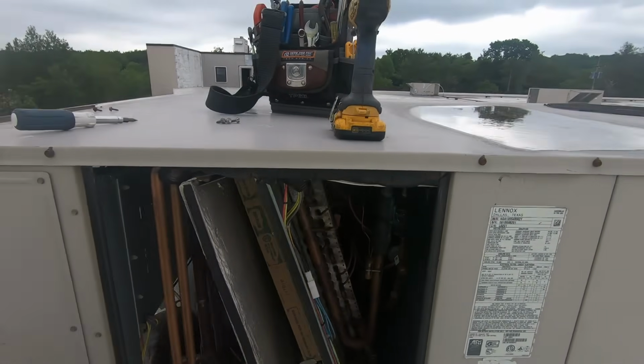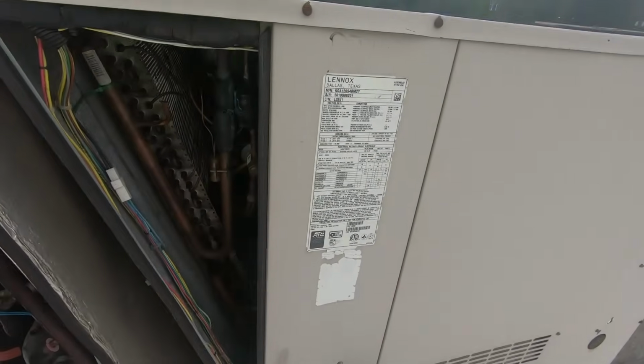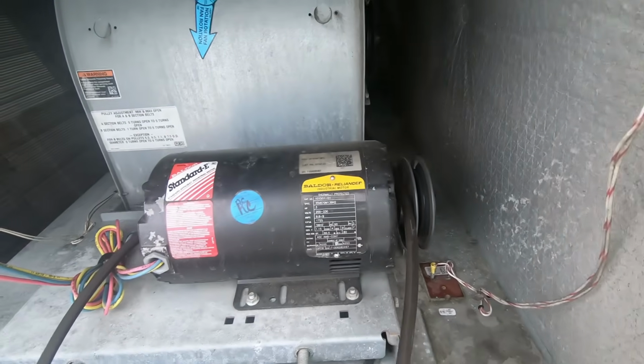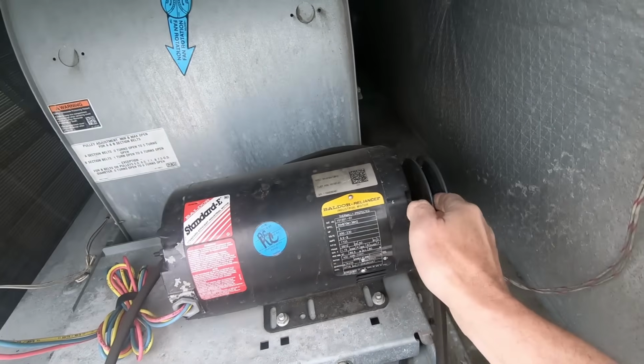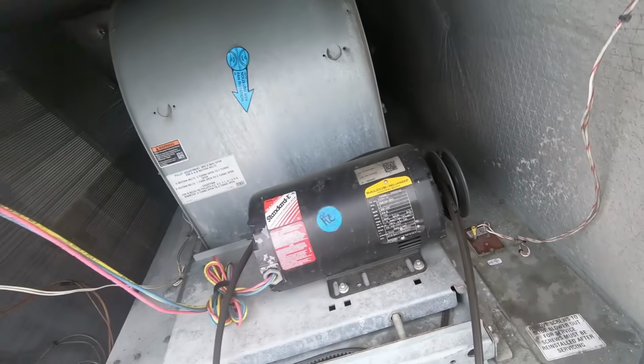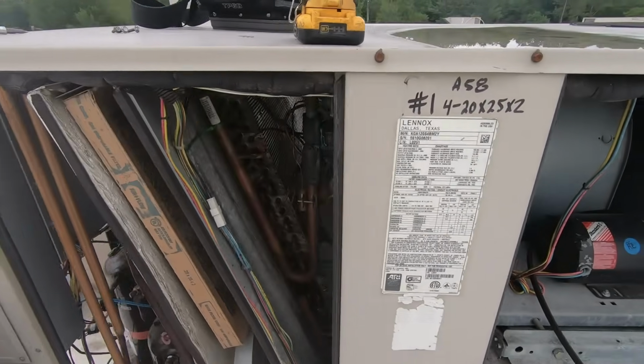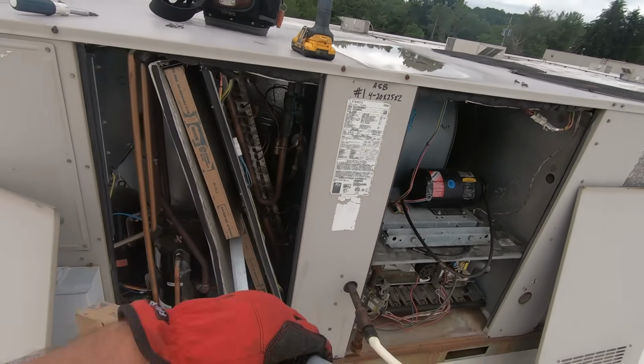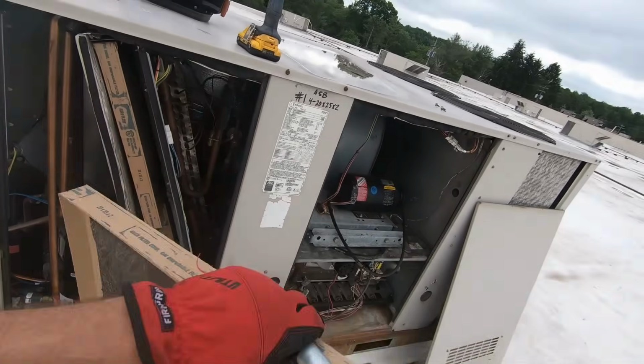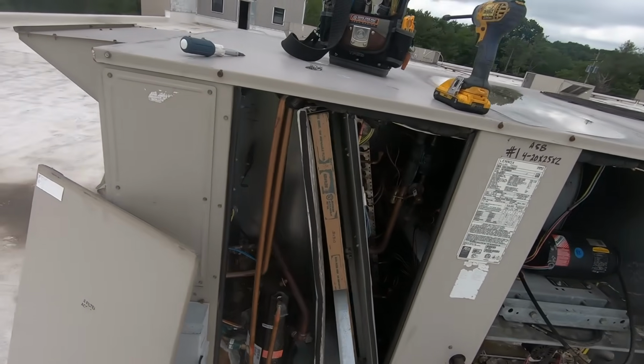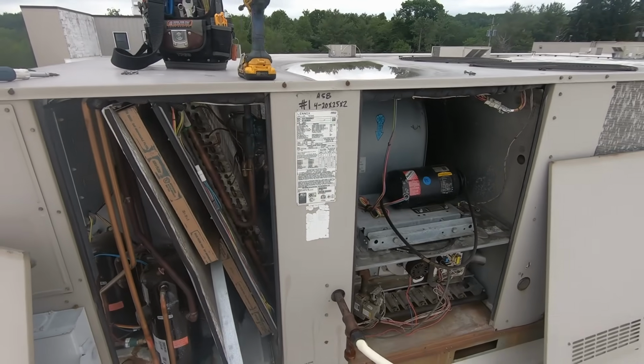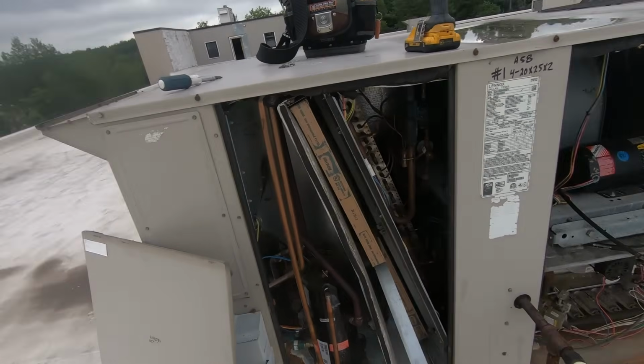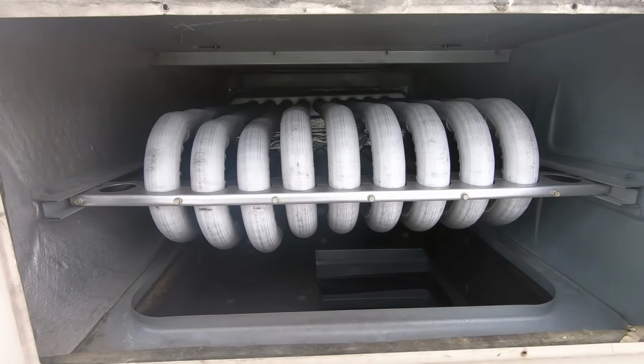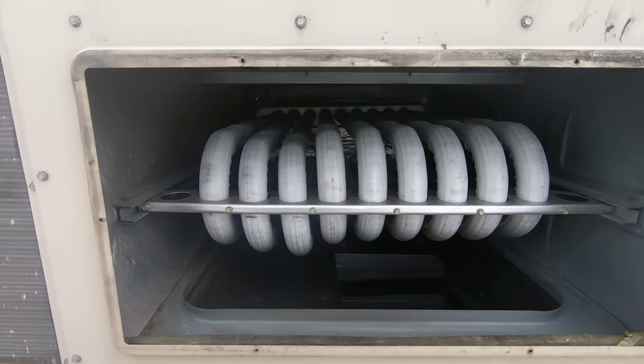Shut it off. Belt's gonna be freaking beat for sure. The belt's worn, the pulley is decent, not too much I'm finding on that blower. It's just a shaker. Filter, dirty. I'm gonna look over this electrical, check the heat exchanger, cycle it in air conditioning, and if it works, it works. If not, I'm moving on. Well, the heat exchanger's good.